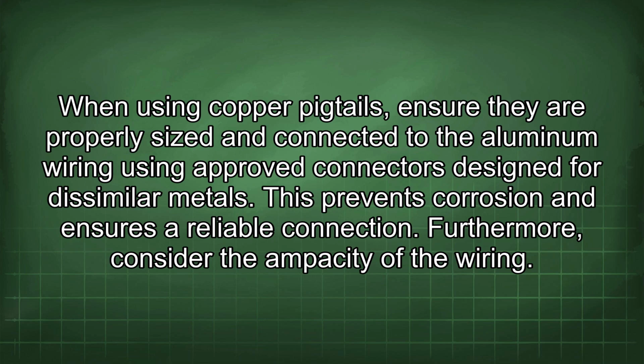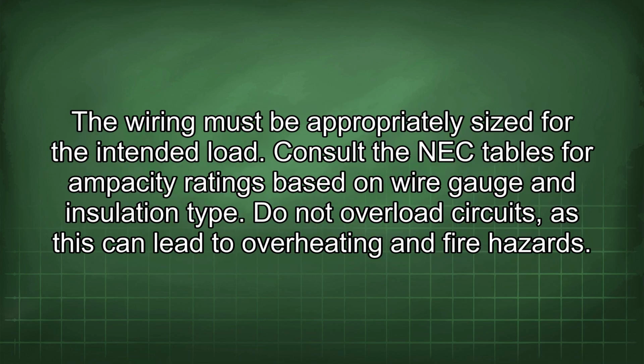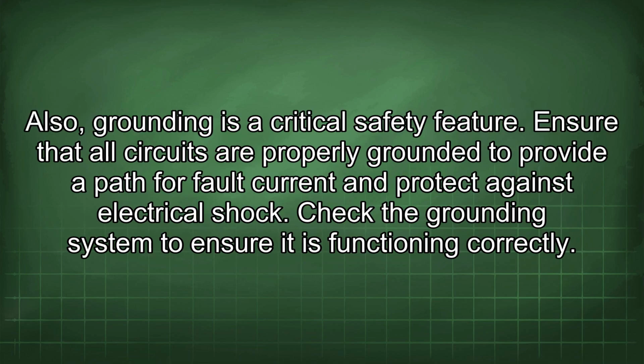Furthermore, consider the ampacity of the wiring. The wiring must be appropriately sized for the intended load. Consult the NEC tables for ampacity ratings based on wire gauge and insulation type. Do not overload circuits, as this can lead to overheating and fire hazards. Also, grounding is a critical safety feature. Ensure that all circuits are properly grounded to provide a path for fault current and protect against electrical shock. Check the grounding system to ensure it is functioning correctly.